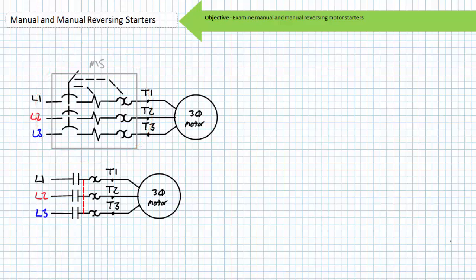Additionally, you may see a manual motor starter represented schematically as a set of primary contacts in series with an overload with a dashed line across it. The dashed line indicates this is a manual motor starter and necessitates no pilot coil, nor does it use any auxiliary contacts.